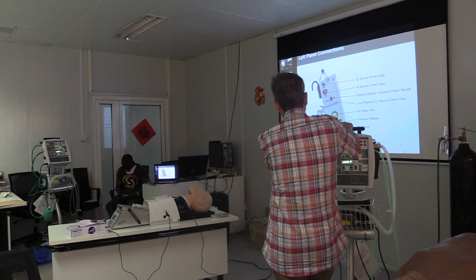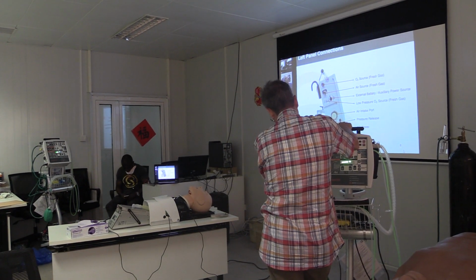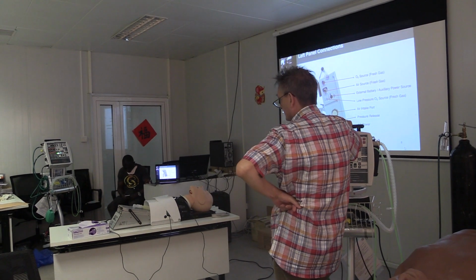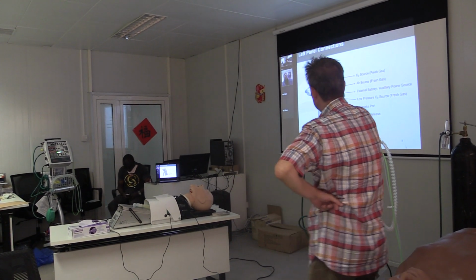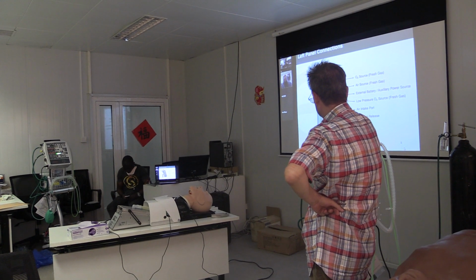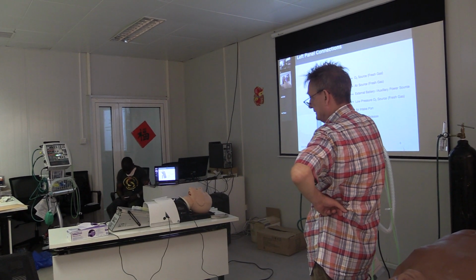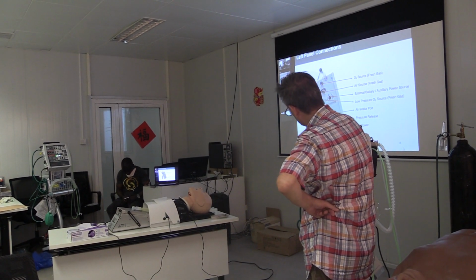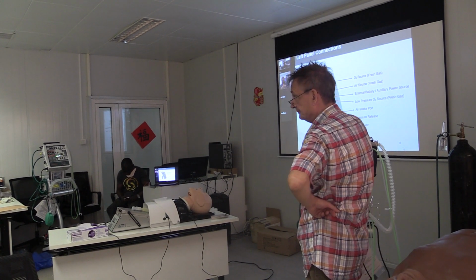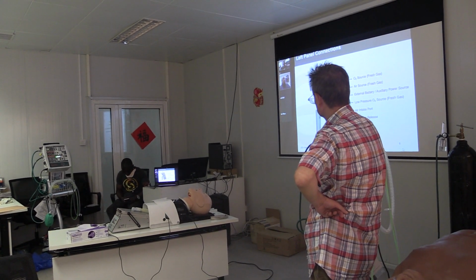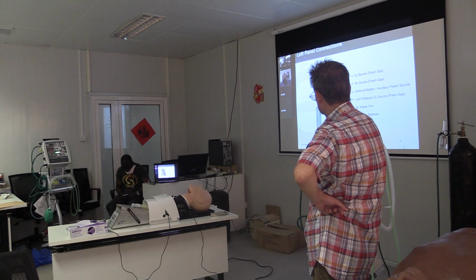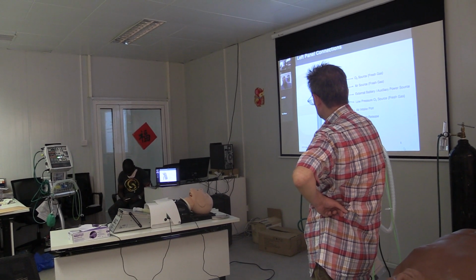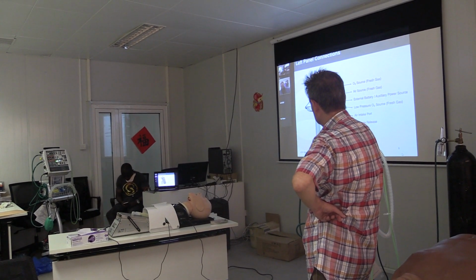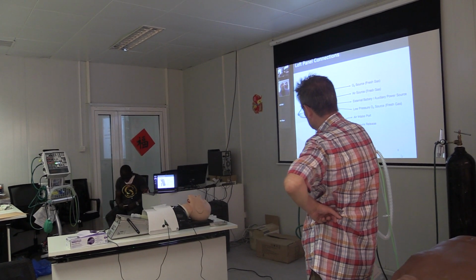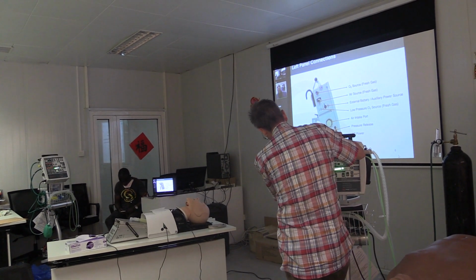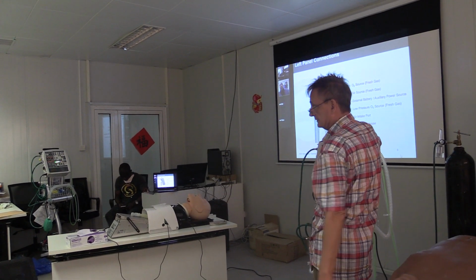Because when you take that black covering off, there's a sponge under there, which is a filter, because that's where your air is coming into the ventilator to dilute with your oxygen to make your different percentages of oxygen that you're giving to the patient. So never cover. You have to just make sure that that's never covered. Because if that's covered, then the ventilator is going to really struggle.